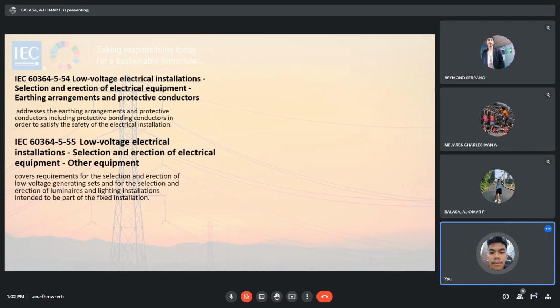Where the supply to an installation is at high voltage, requirements concerning the earthing arrangement of the high voltage supply and of the low voltage installations shall also comply with Clause 442 of IEC 60364 Part 44, I mean. The requirements for earthing arrangements are intended to provide a connection to earth which is reliable and suitable for the protective requirements of the installation, can carry earth fault currents and protective conductor currents to earth without danger from thermomechanical and electromechanical stresses or from electric shock arising from these currents, if relevant is also suitable for functional requirements, and is suitable for foreseeable external influences. Example nito is yung mechanical stresses and corrosion.